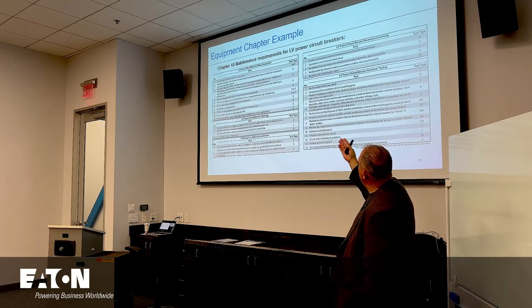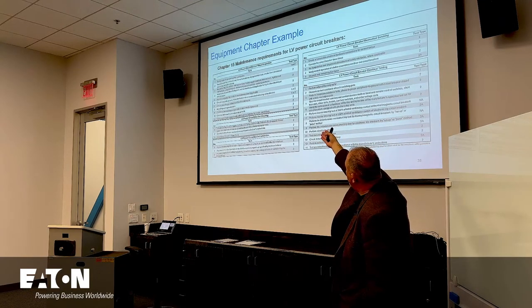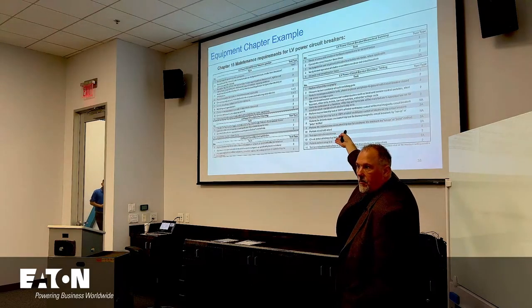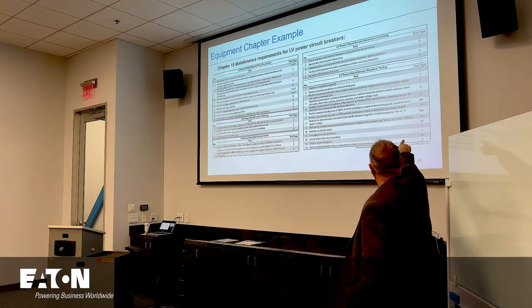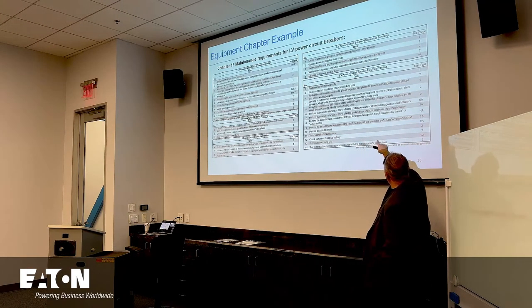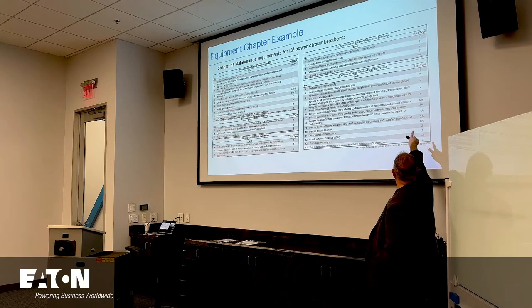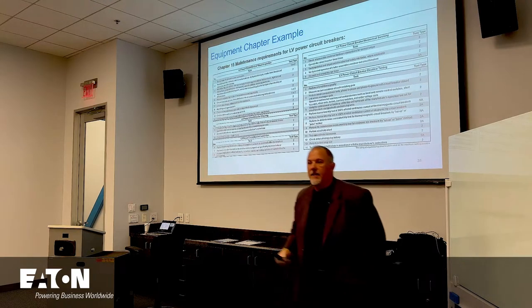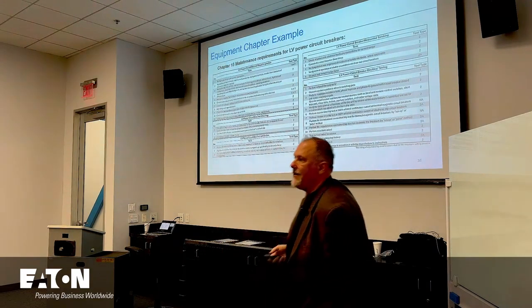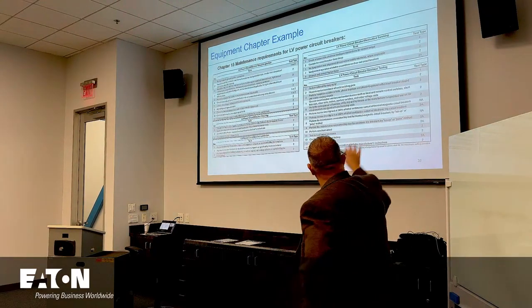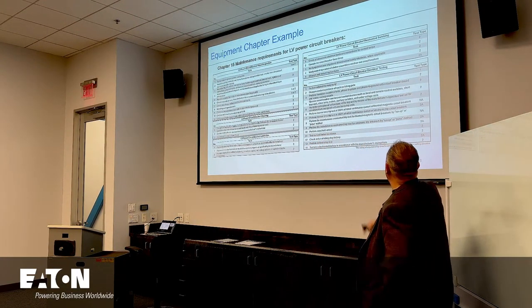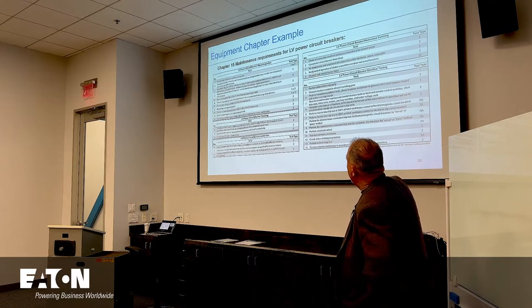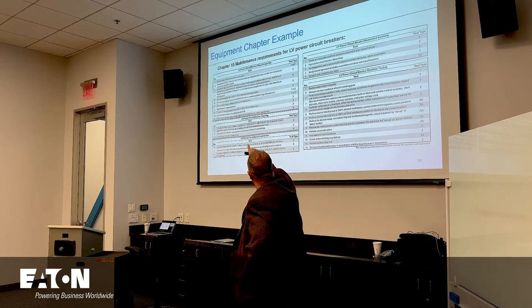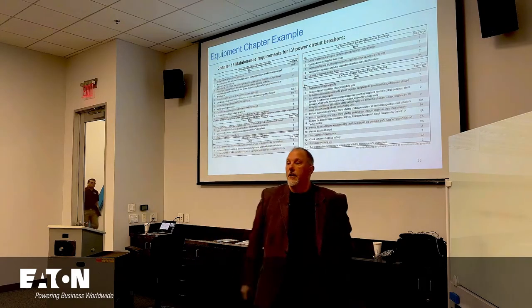So here's low voltage power circuit breakers. You've got the tasks, whether it's a 1 or a 2, do it energized or offline. And if there's a 1A or a 2A - perform the instantaneous overcurrent trip test for electronic trip breakers by run-up or pulse method, that's a 2A, an enhanced test. If you didn't get results on something that you didn't quite like, then you're going to want to focus on doing some of these 2A or 1A tests. In some cases it'll be a 1 or a 2, like check for cracks or lack of visual indication for all associated indicated status devices - you can do that either energized or not.